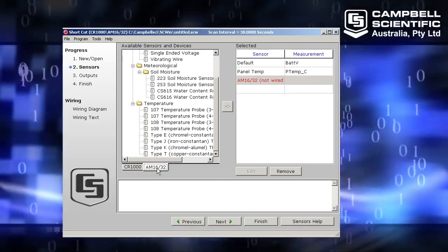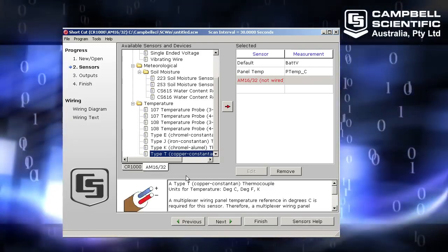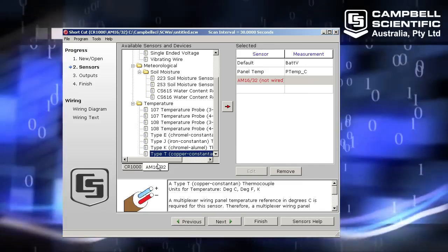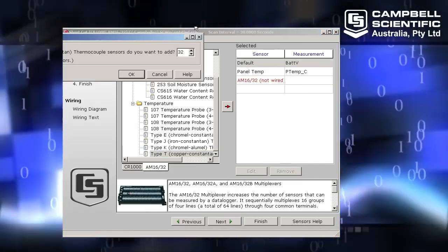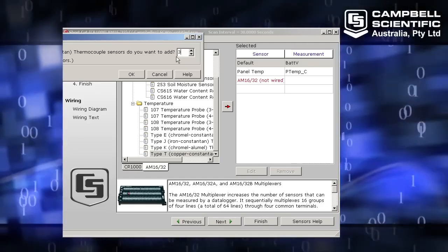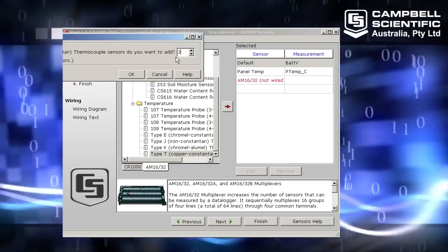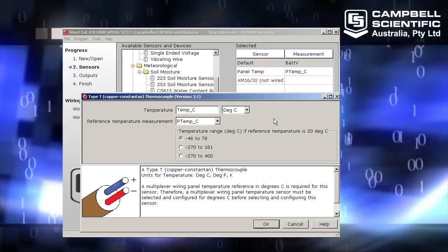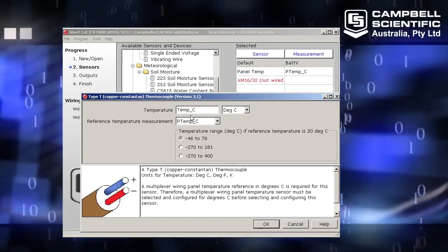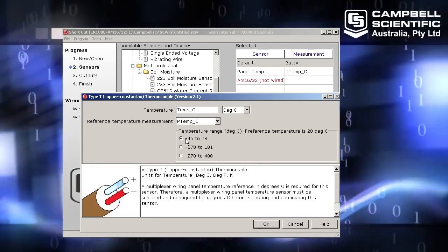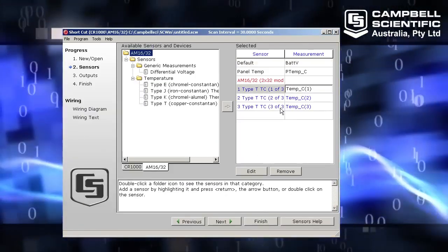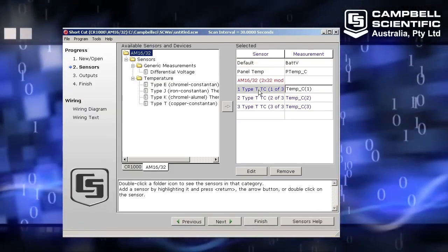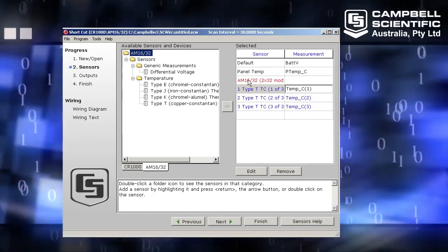I'm going to choose the AM1632 and then choose a type T thermocouple. Now when I add this, it will be added to the multiplexer instead. So click the add button. I have wired three thermocouples into my multiplexer, so I'll change that number to three and click OK. I have some options to do with the thermocouple measurement itself. I'm going to leave all of those as the default, the name and the temperature range, and click OK. So I can see here I have three thermocouples added underneath my AM1632.